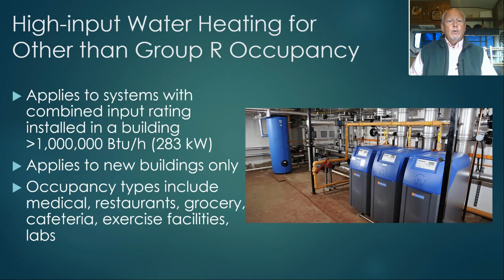So high input water heating for other than Group R occupancy applies to systems with a combined input rating installed in a building greater than 1 million BTU an hour, or equivalent 283 kW. It applies to new buildings only, although I'll mention maybe perhaps some alterations where this could affect you. And these occupancies other than Group R would include medical, hospital, restaurants, grocery, cafeteria, exercise facilities, and labs.